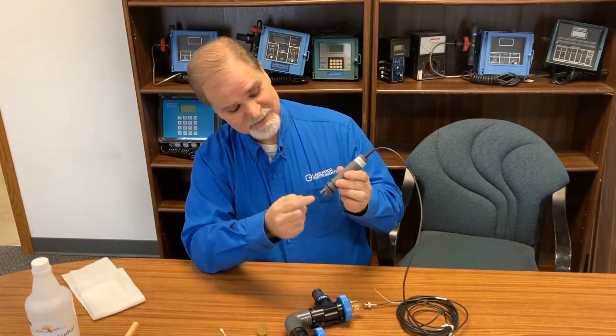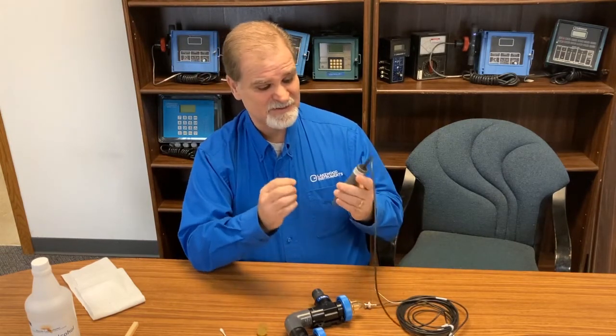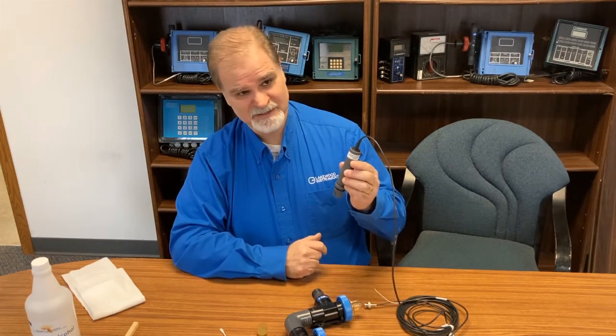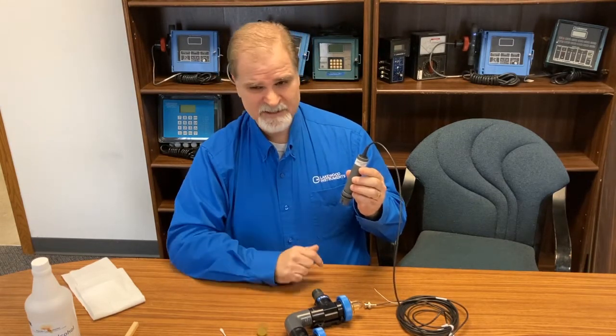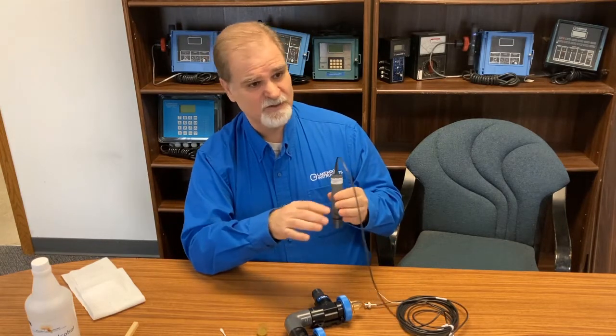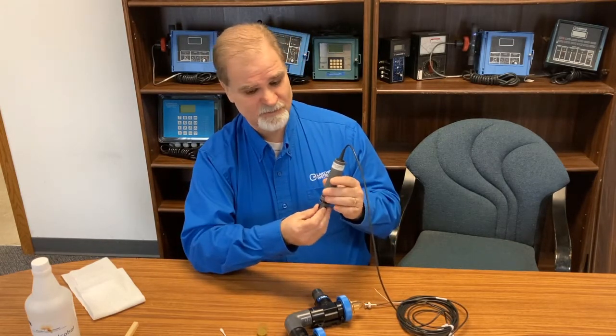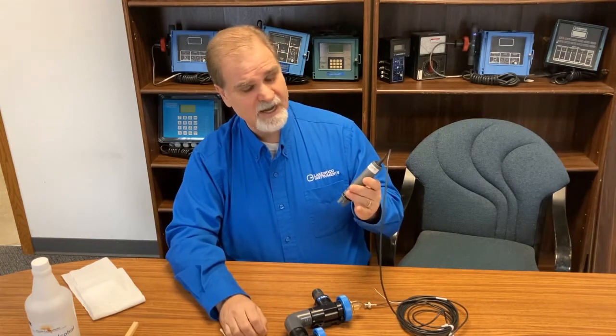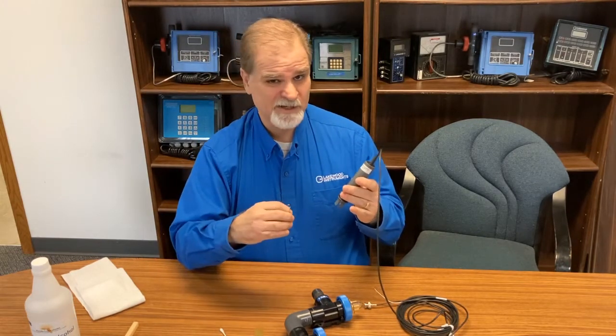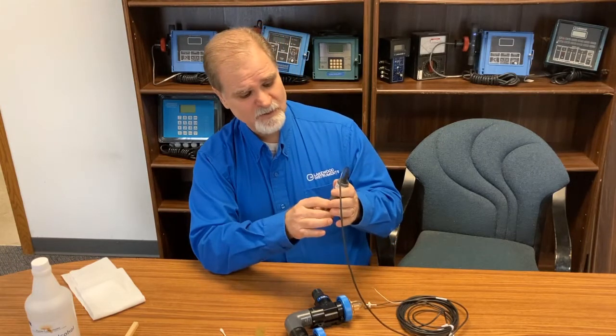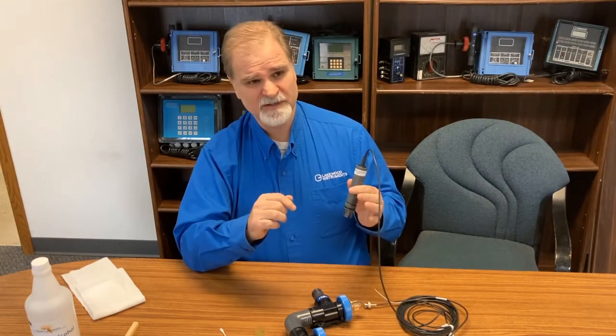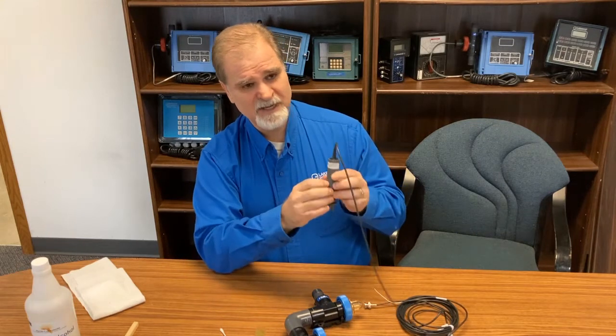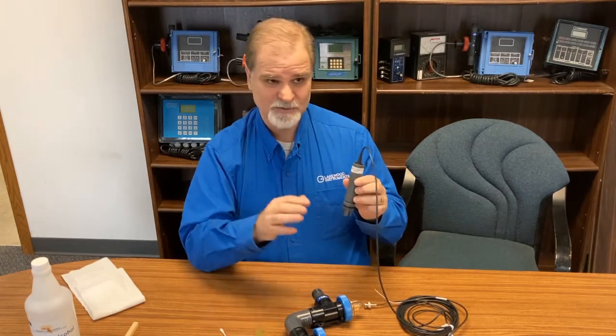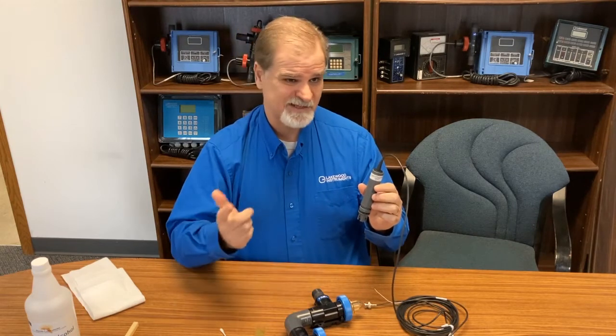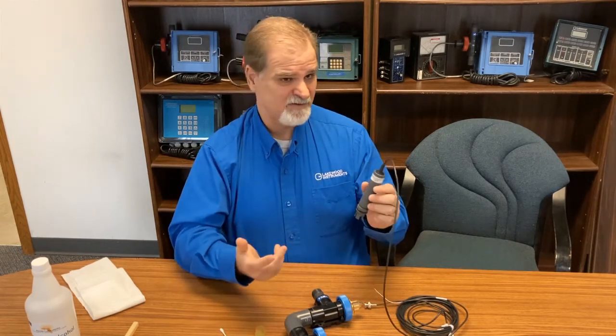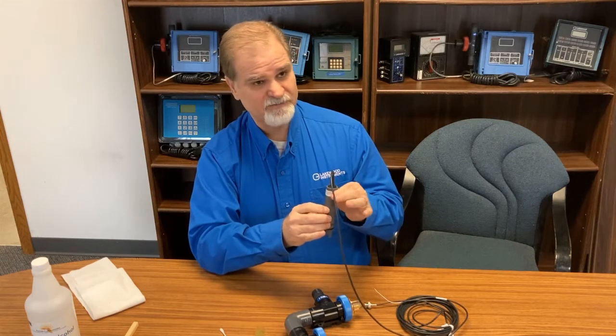We may have mentioned that these electrodes are made of glass. Well, that means that there's a maximum pressure limit on these glass electrodes. It's typically in the range of 100 to 150 psi, and if you go above that the glass can break and the sensor won't work. They also have a high temperature limit. Even though we talked about winter months where freezing is the limit, they can go up to typically about 212 degrees Fahrenheit, but the sensor body may not be able to handle that. So you need to check and make sure which sensor you have, whether it's a stainless steel, CPVC, or PVDF, and that has a specific temperature rating for that also.